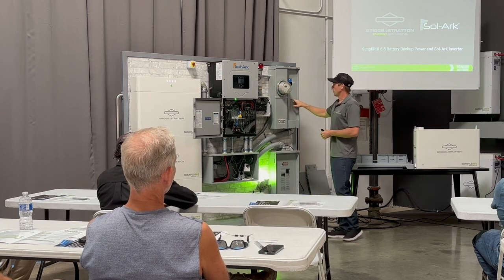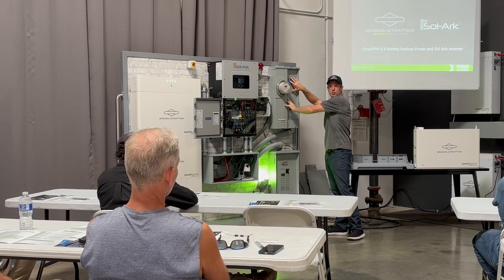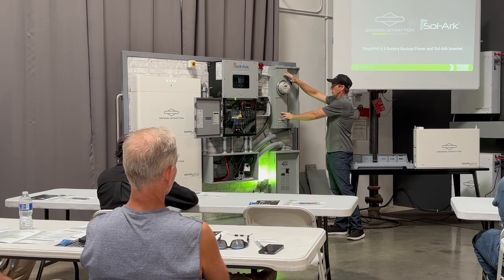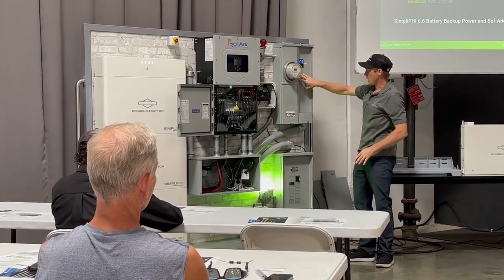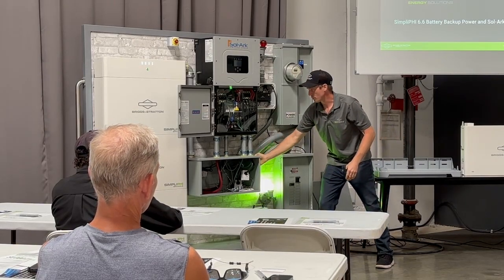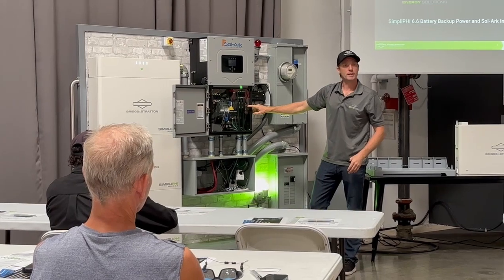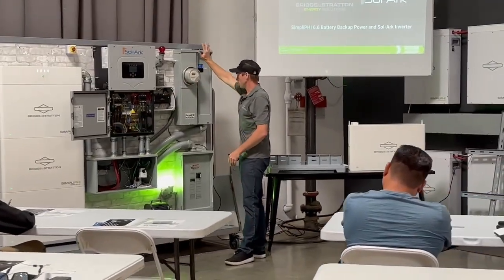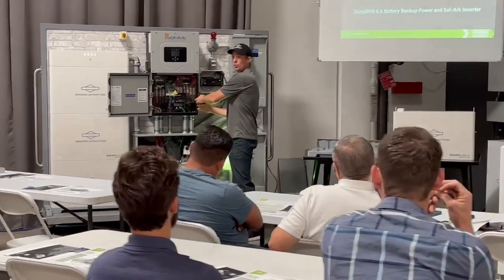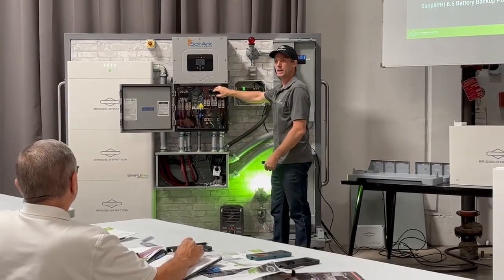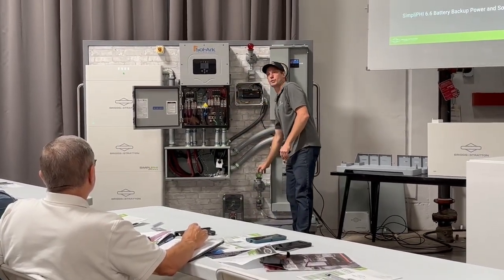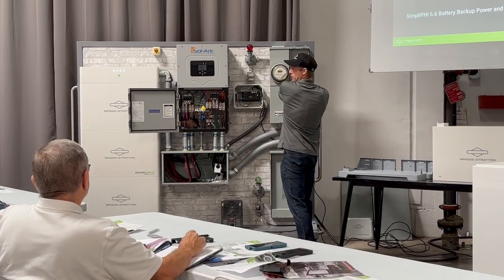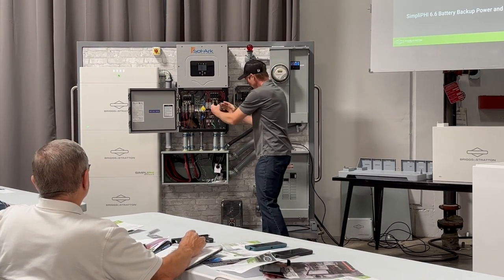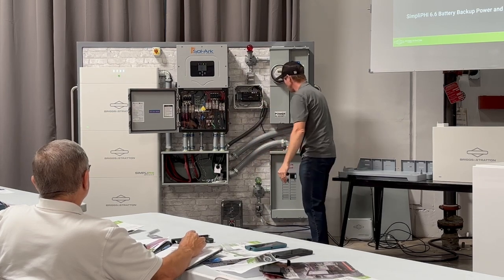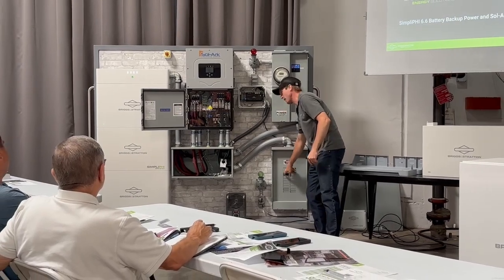And so we're doing that with 3-aught cabling. So this is my service entrance. So this is to represent here in California the service entrance with 200 amp service, and that's wired in. And so I've got my utility connection coming through here and coming up into the right side of the inverter. So that's a 200 amp connection coming in. So my utility connection is this. All of that power with the Sol-Ark 15K passes through the inverter relays and passes out to the loads. So this is my load disconnect here. So if I pull this, I've killed the loads for my load panel. So we come in from the utility into the inverter, we come out of the inverter and into the loads, right? So my loads panel is here. I only have a single 15 amp, 20 amp breaker here.